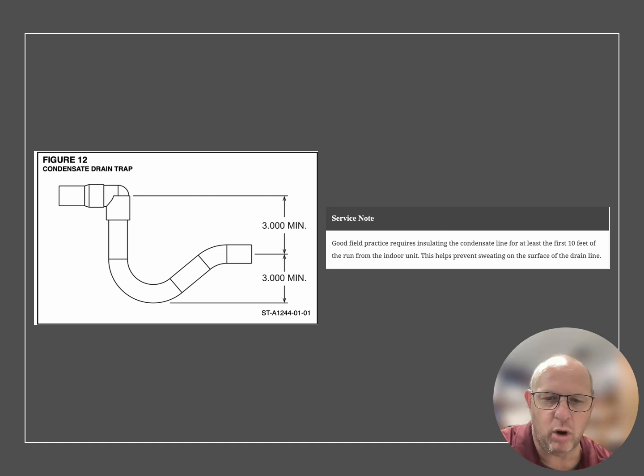So good field practice is required to insulate that condensate line as it's coming off of the indoor unit at least 10 feet away, especially if you're in an attic or an area where you have high moisture. So that line will actually sweat and will cause damage to surrounding drywall, surrounding wood, or other types of materials that can be destroyed by that condensation.